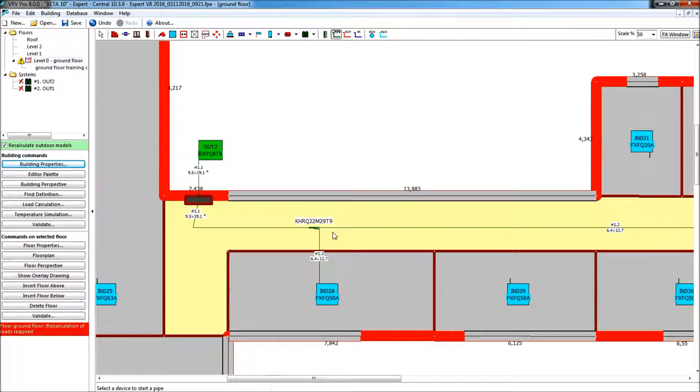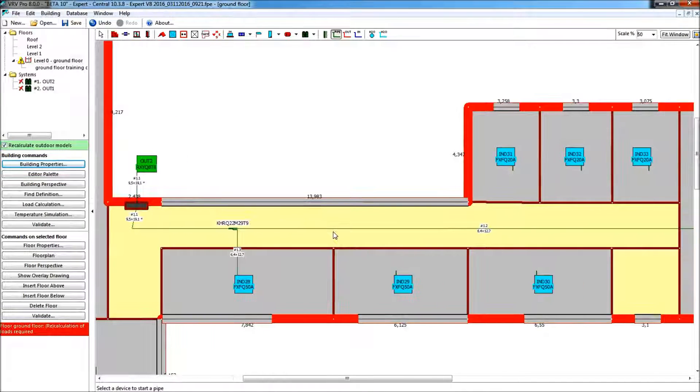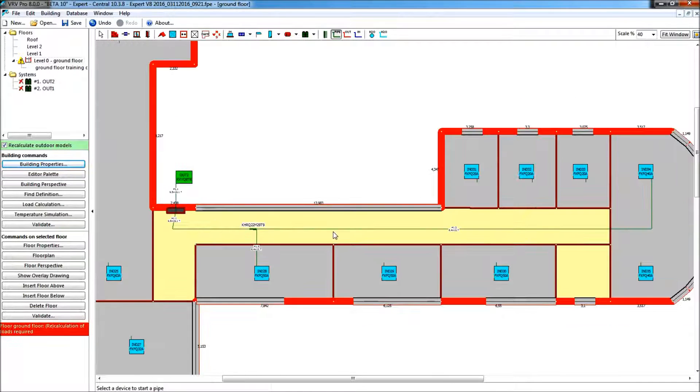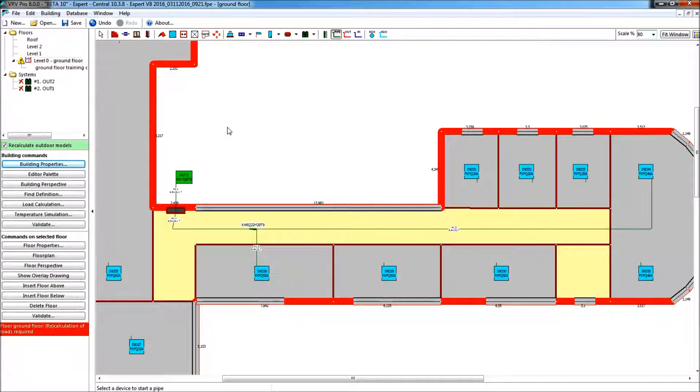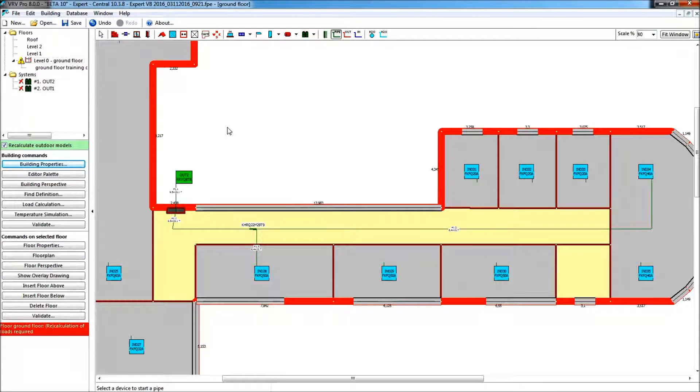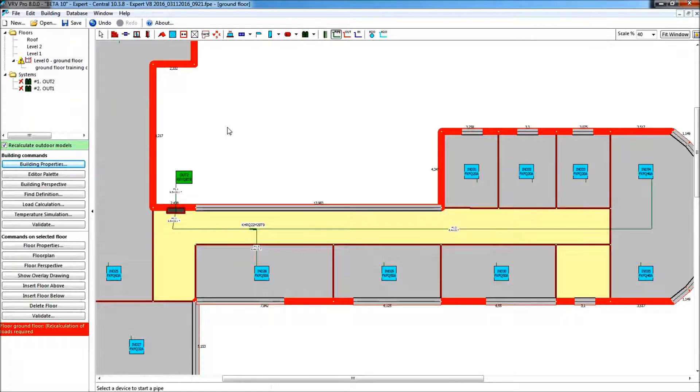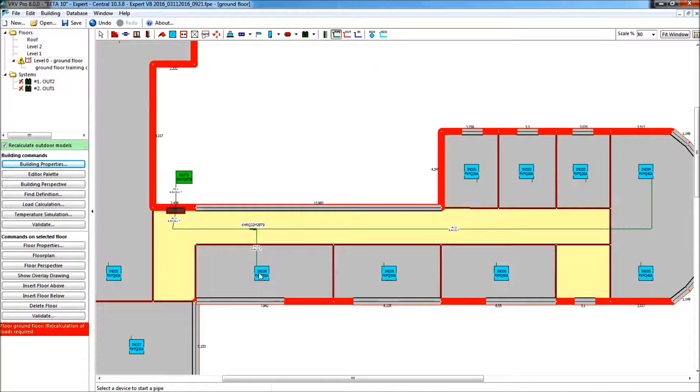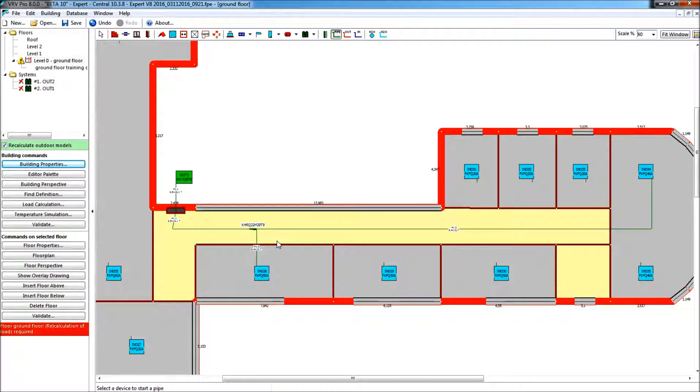But the fact that I did connect the shortest connection as well, this gave the possibility for the program to, on the fly actually, check my piping rules. And in here we did check two things. The golden rule that longest piping minus shortest piping after first branch cannot exceed 40 meters. Well, it can, but it has consequences. And the second, that the longest distance from an indoor unit to its nearest branch would never exceed 40 meters.